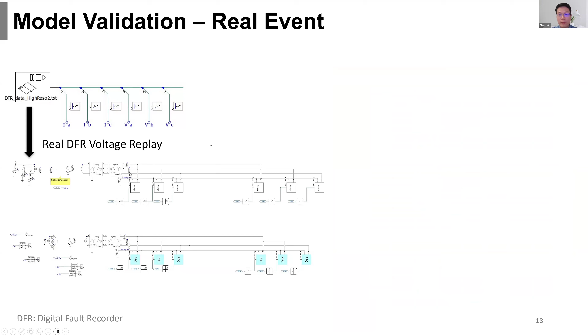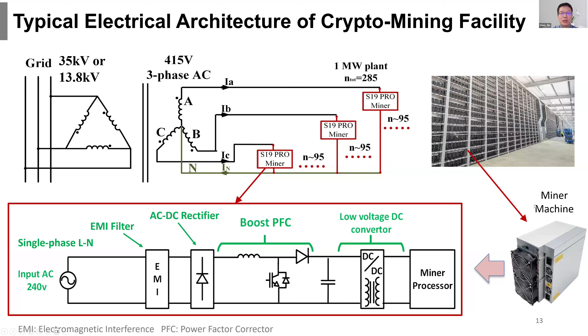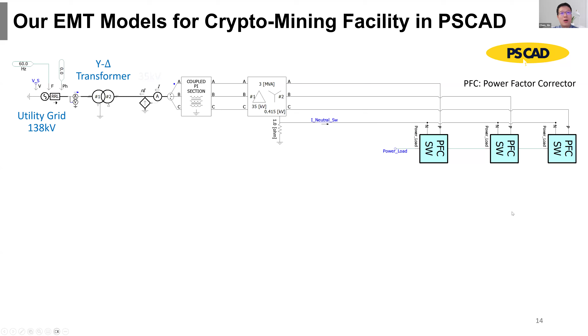For the miner machine, we can set the power reference because we can change the hashing rate, and different hashing rates are associated with different power references. But we have also done testing for the miner machine, and their behavior is like a constant power load. For example, if we lower the voltage, the current from the miner machine will increase. Then if we compute the power, we can observe that the overall power from the miner machine at different voltage conditions is kind of constant. That's why we model the crypto miner machine as a constant power load, but this power can be the power reference we can set.